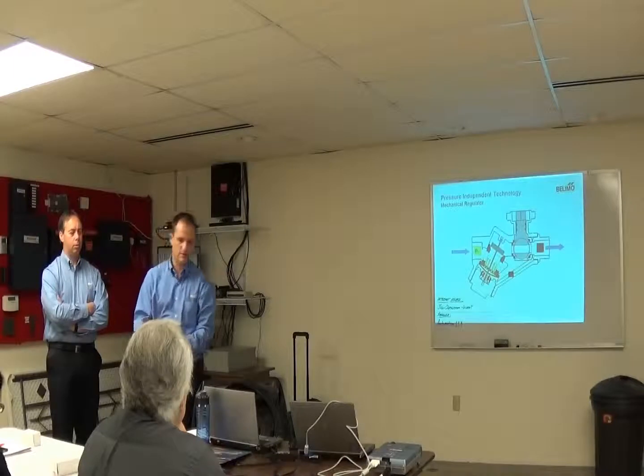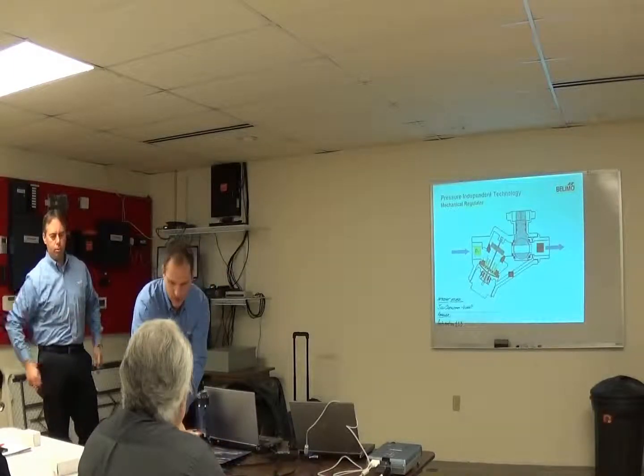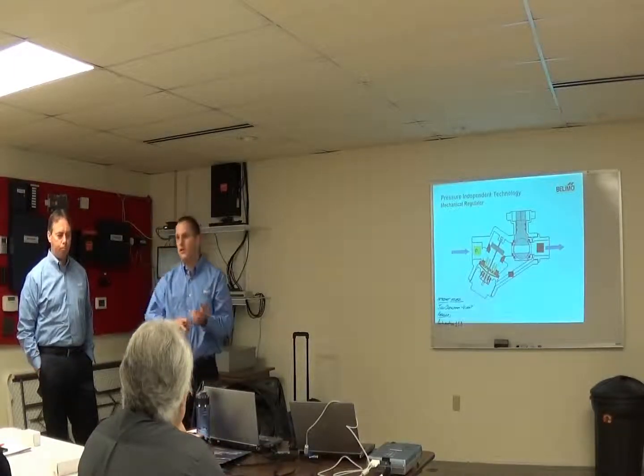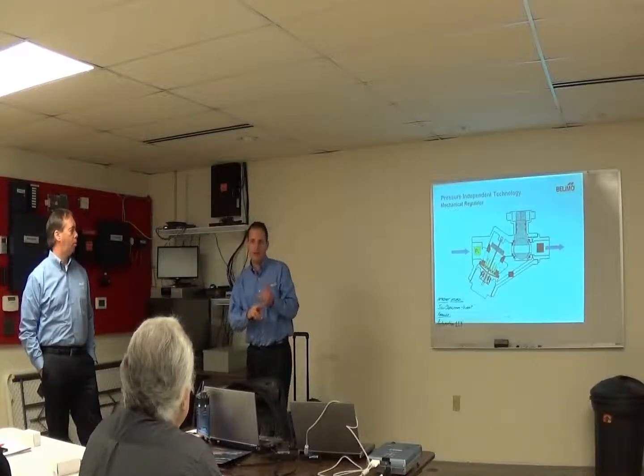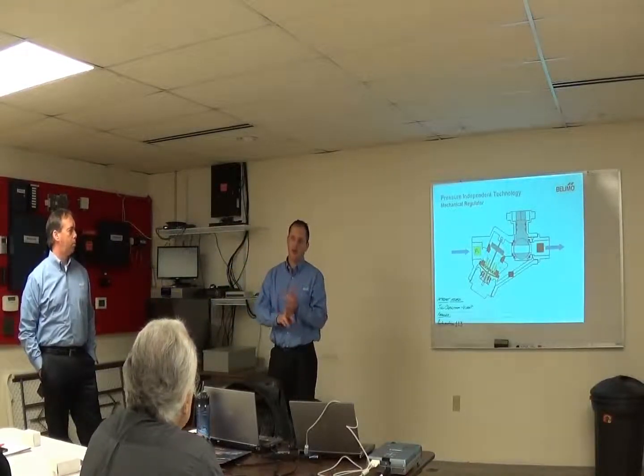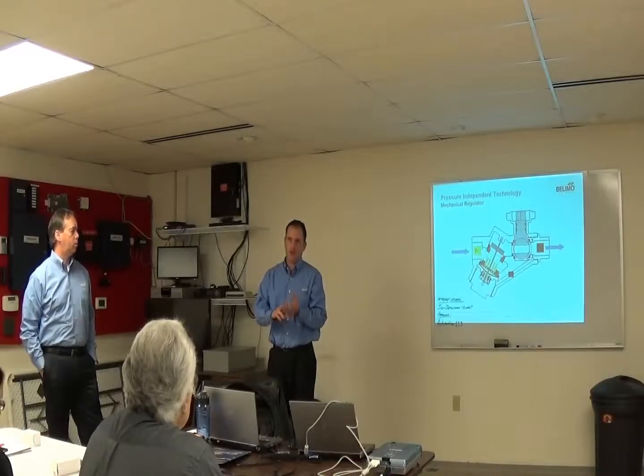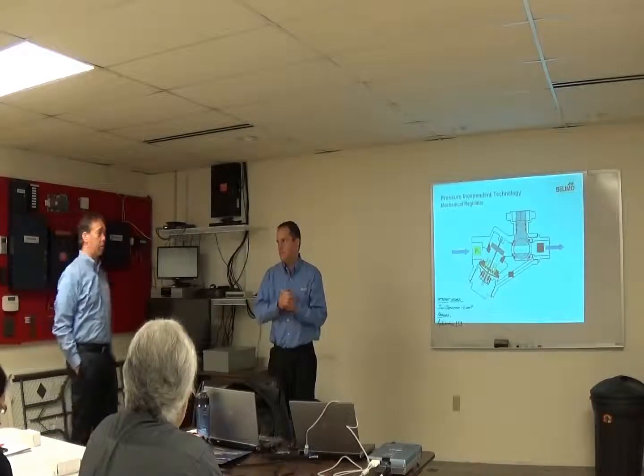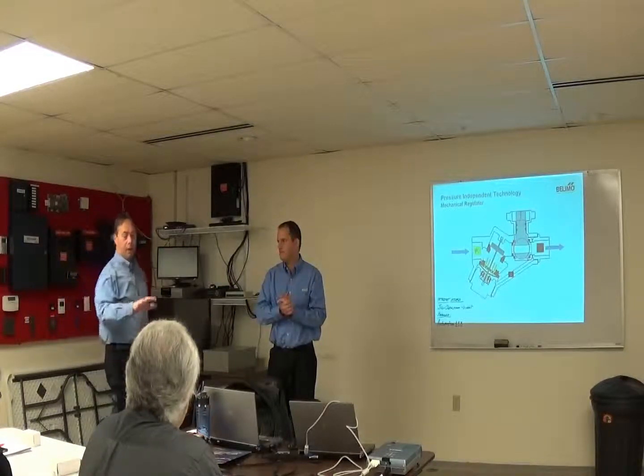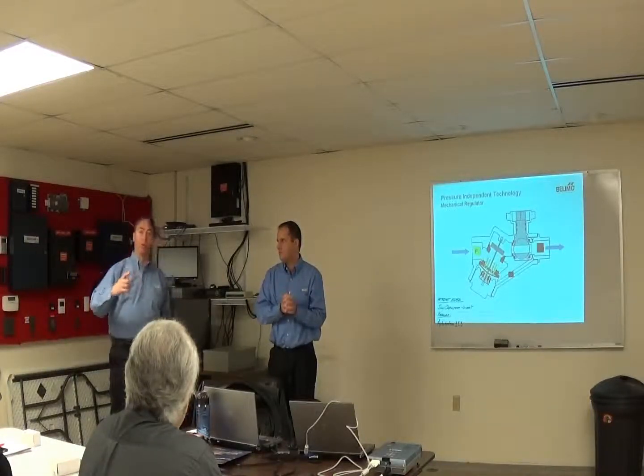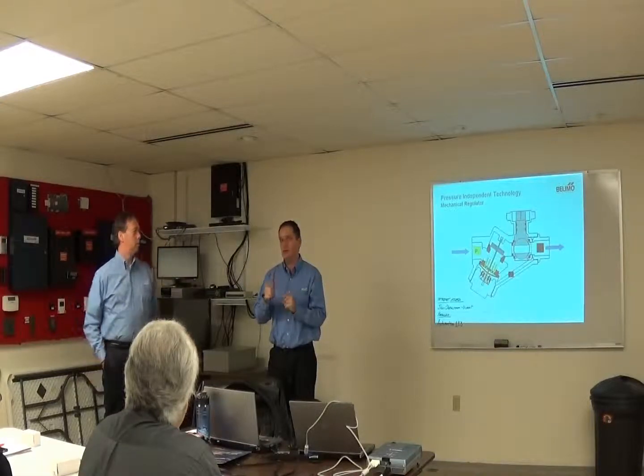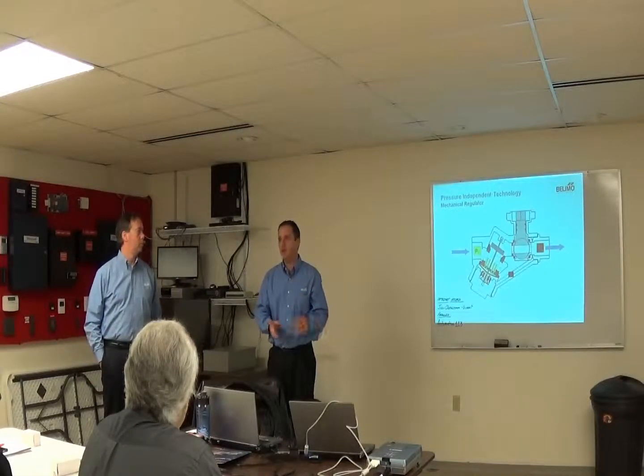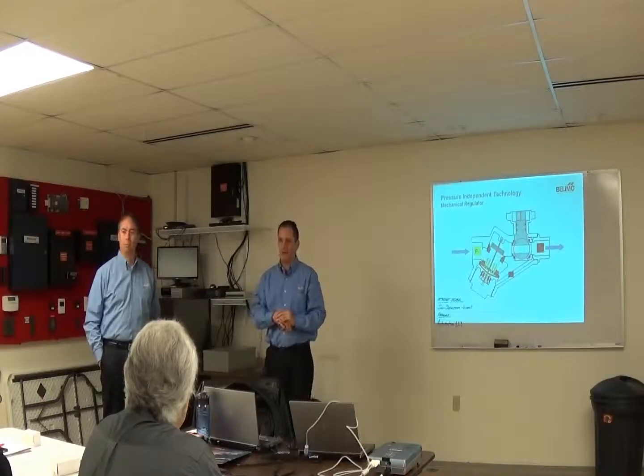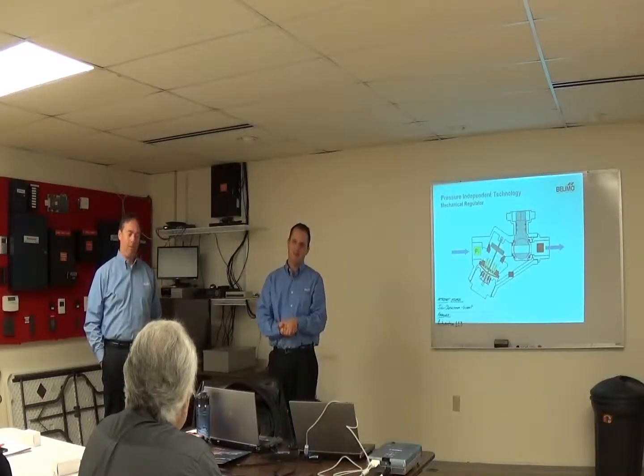So Don kind of talked about it, but you can set this up as a pressure dependent valve, and then you can also turn on delta T manager or power control as a pressure dependent valve. Same way with pressure independent, you can turn on delta T manager or power control. And the other thing I didn't mention, all the data collection can be done in any of those modes as well. As soon as you plug the valve in and put power on it, you're getting data. You can't stop it. It's going to collect data for the life of the valve, you cannot stop it.